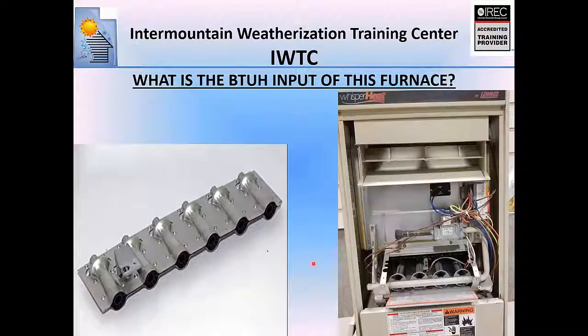All right, so you're an auditor. You're out on a furnace, and the tag on it is missing. You need to know what the BTU input is because you've got to put that into the audit, right? You have nothing on the furnace to tell you what it is. So here is a quick trick to help you with that. Count the number of burners and times it by 20,000. So in this case, I got 20, 40, 60, 80, 100, 120,000 BTUs. That will work for practically every in-shot burner furnace you run across. There are some oddball ones out there that are 23,000 BTUs per burner, but still, if you use the 20,000 number, it's going to get you really close.